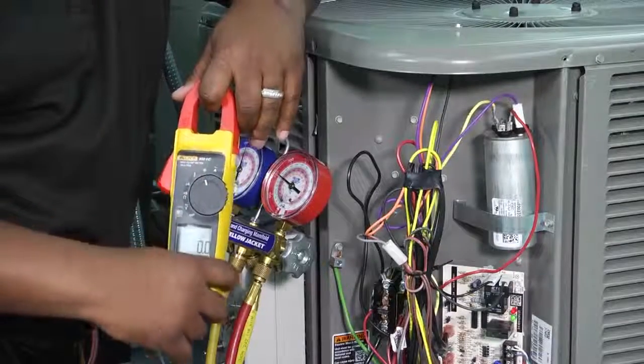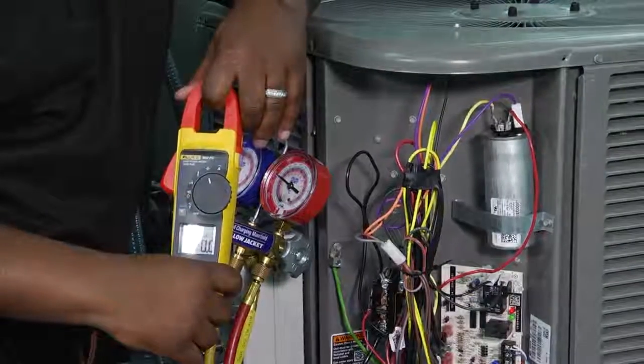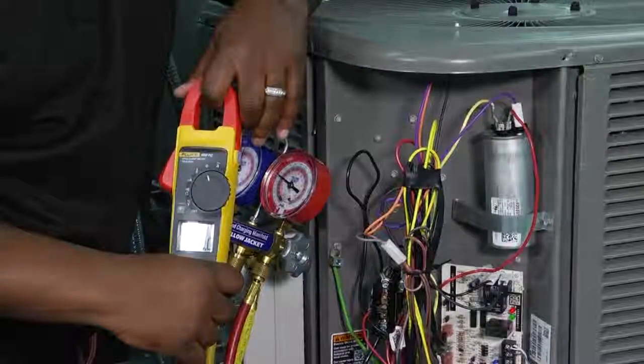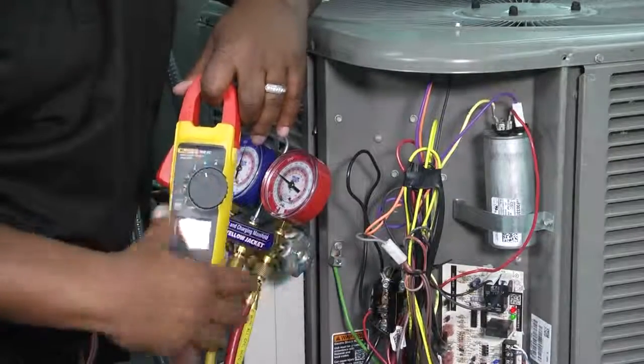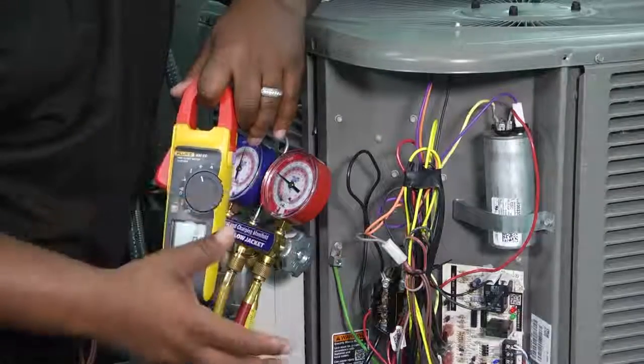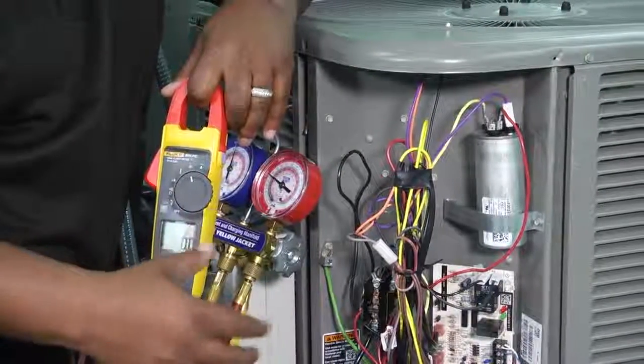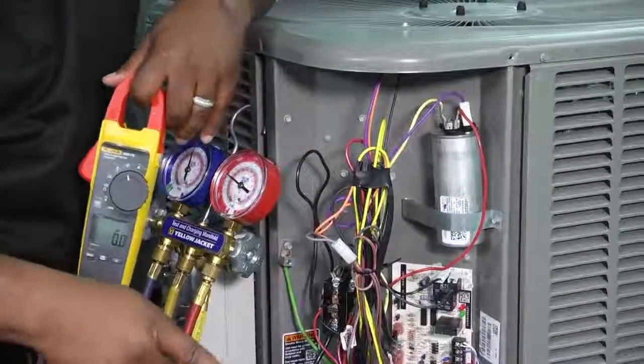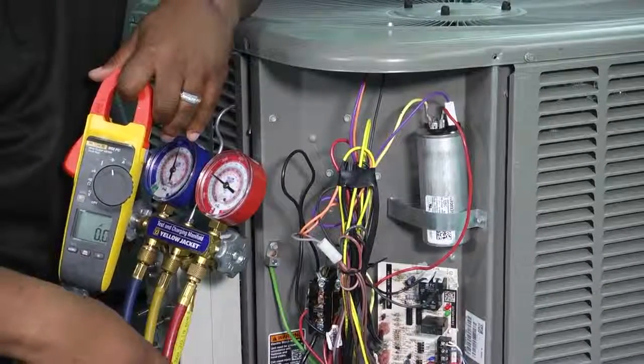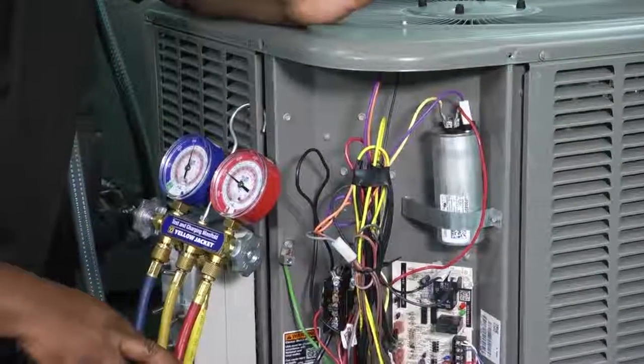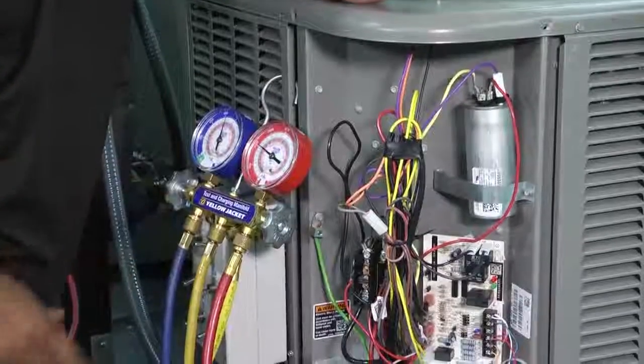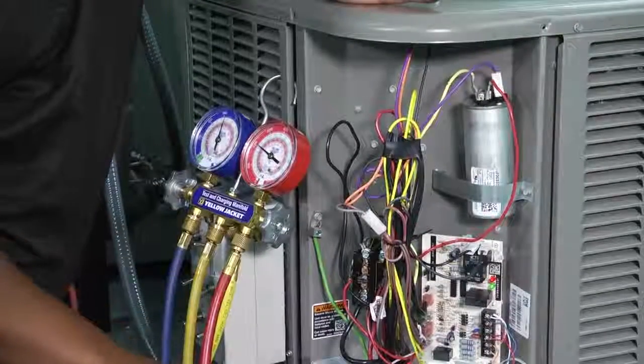And couple that with, maybe we need to talk about our filters. Got to check our filters and make sure our filters have been upgraded, make sure our filters are clean, and we've got a good filtration going through our entire system. As we come back out to our condensing unit, we'll notice I've got my gauges hooked up. My system isn't running, but we're just using this for demonstration's sake, but I have my gauges hooked up.